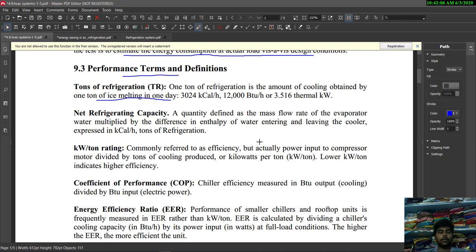The next term is kilowatt per ton rating, commonly referred to as efficiency. It is the power input to the compressor motor divided by tons of cooling produced. A lower kilowatt per ton value indicates higher efficiency.